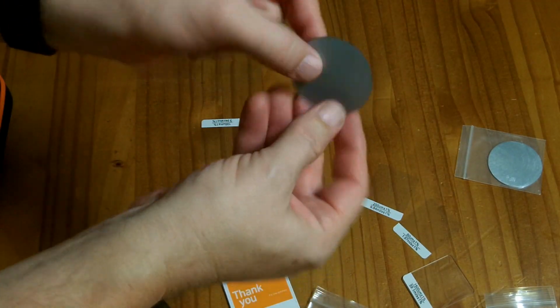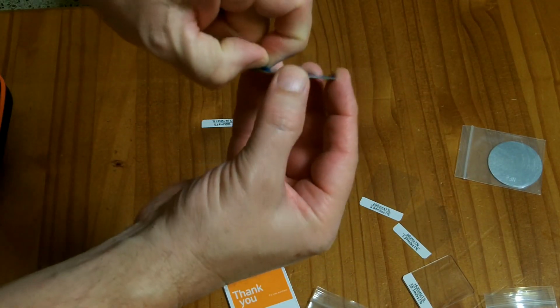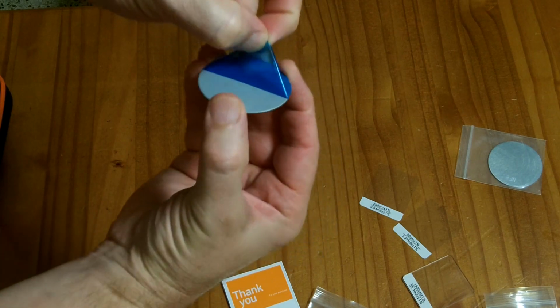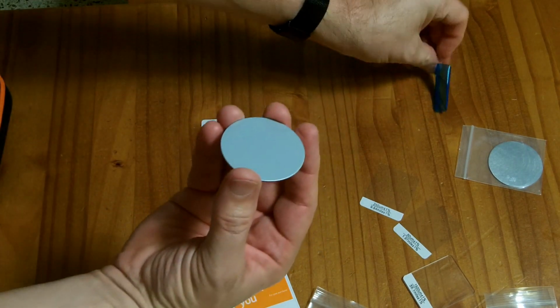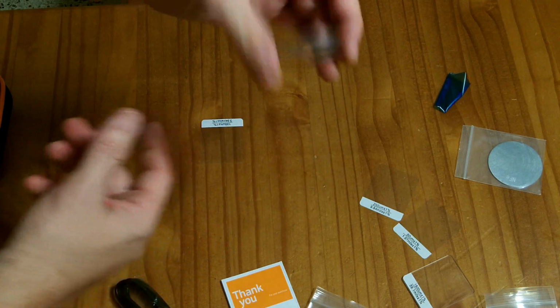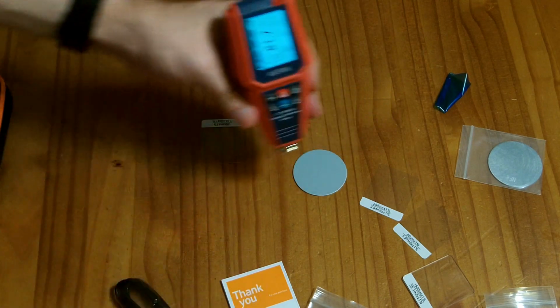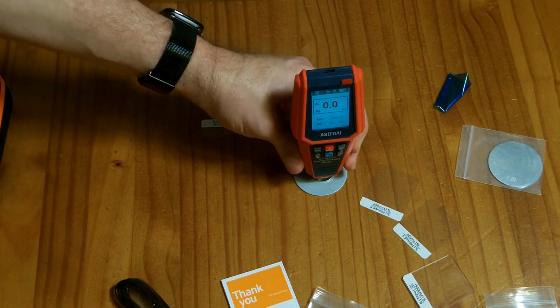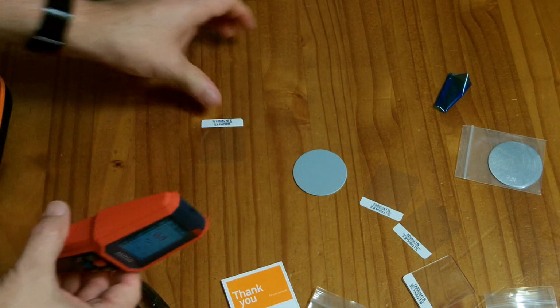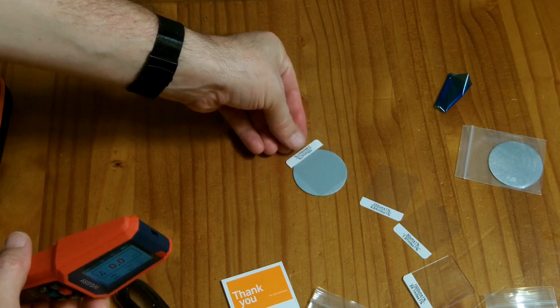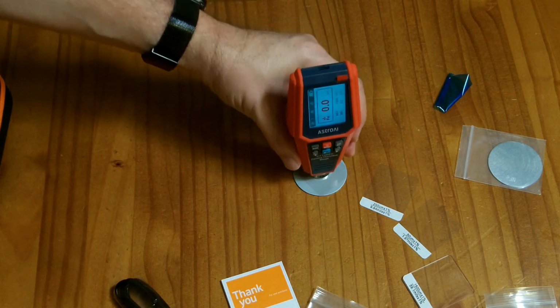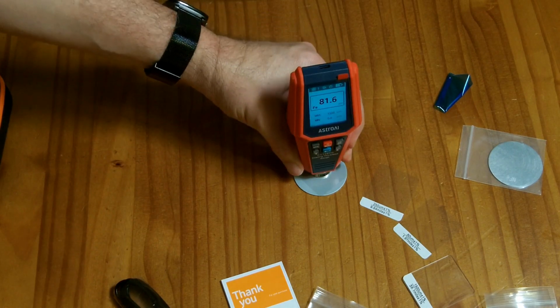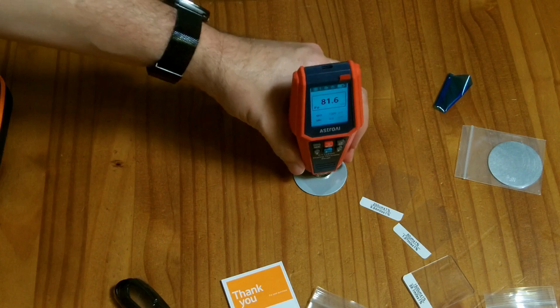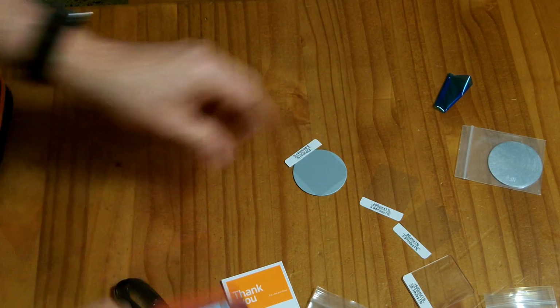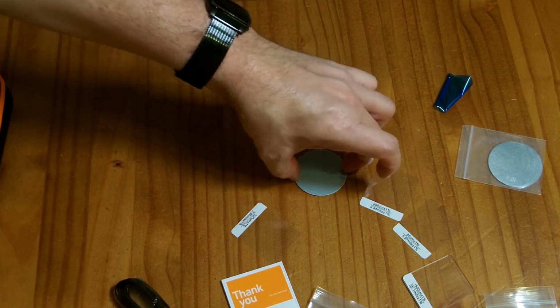Now, this FE disc has a coating on the back, which I believe is a protective plastic coating, and I don't know if we're going to get different readings with this backside with that coating. So it says zero there. I'll put the 100 micrometer, and it's doing 81 here, 82. So it definitely does look like it needs to be calibrated.